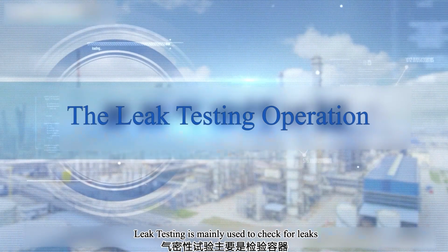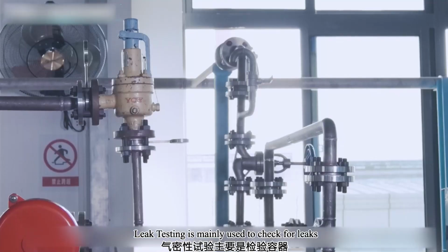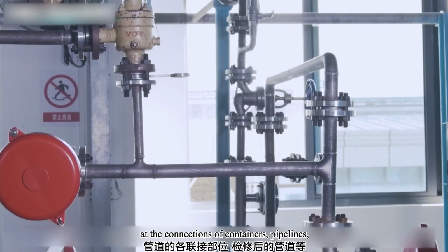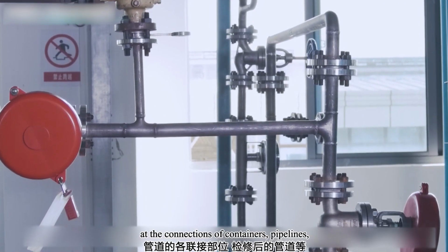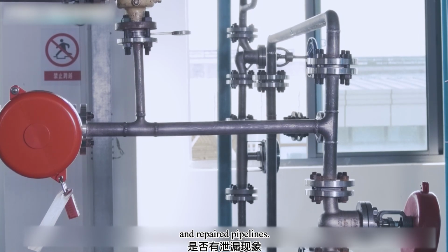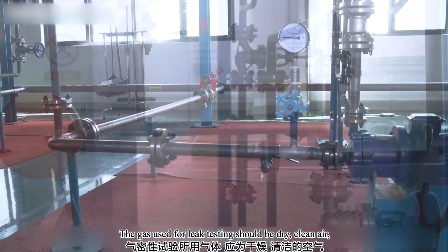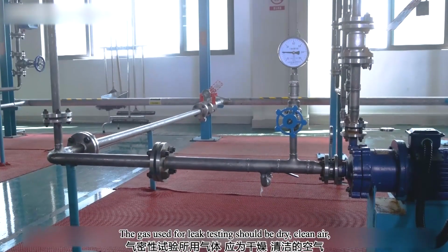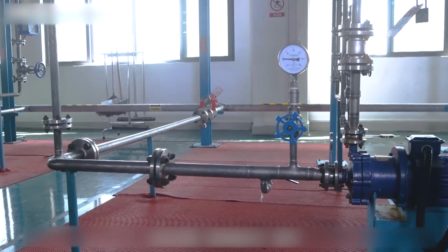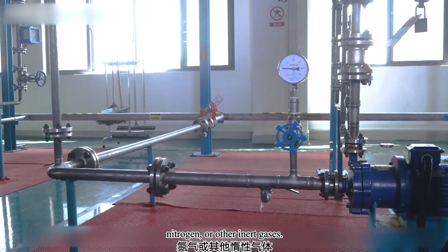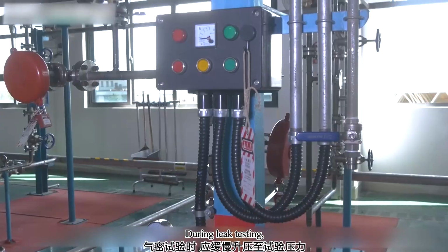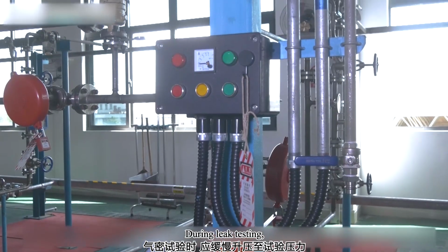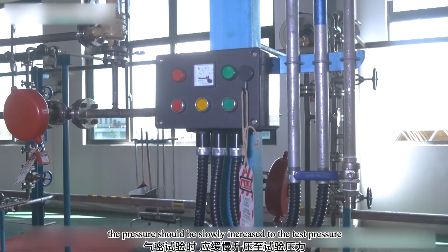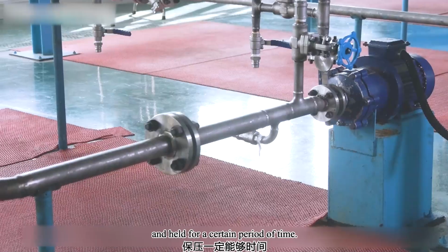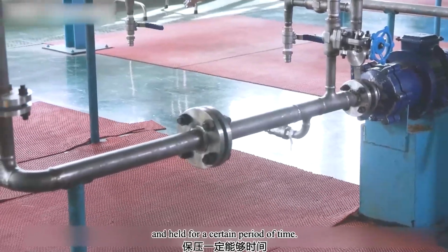Leak testing is mainly used to check for leaks at the connections of containers, pipelines, and repaired pipelines. The gas used for leak testing should be dry, clean air, nitrogen, or other inert gases. During leak testing, the pressure should be slowly increased to the test pressure and held for a certain period of time.